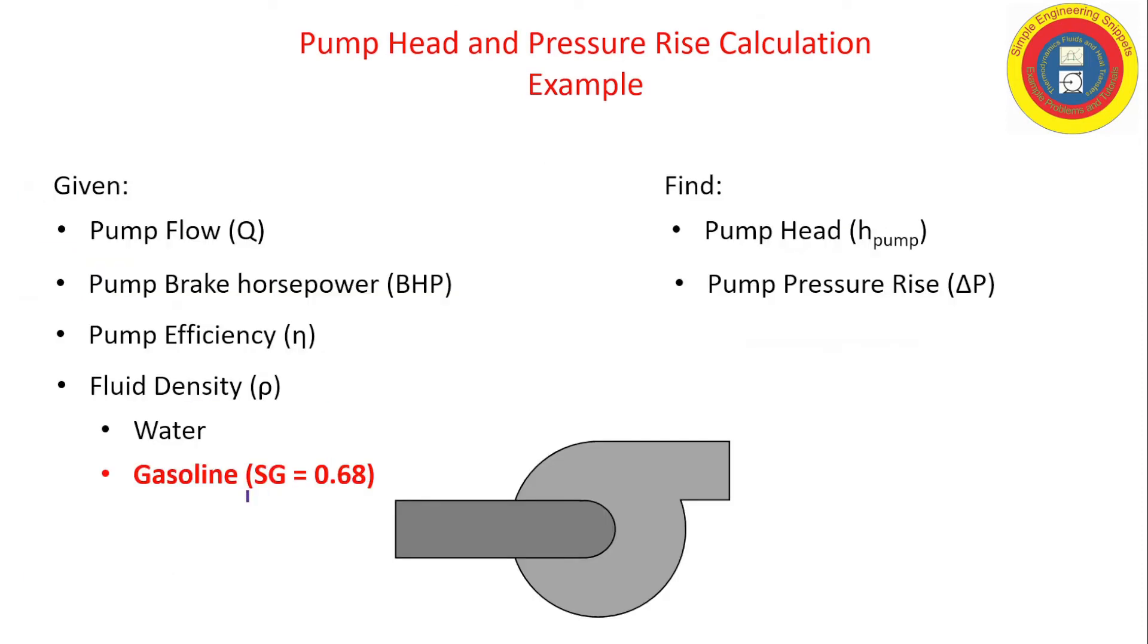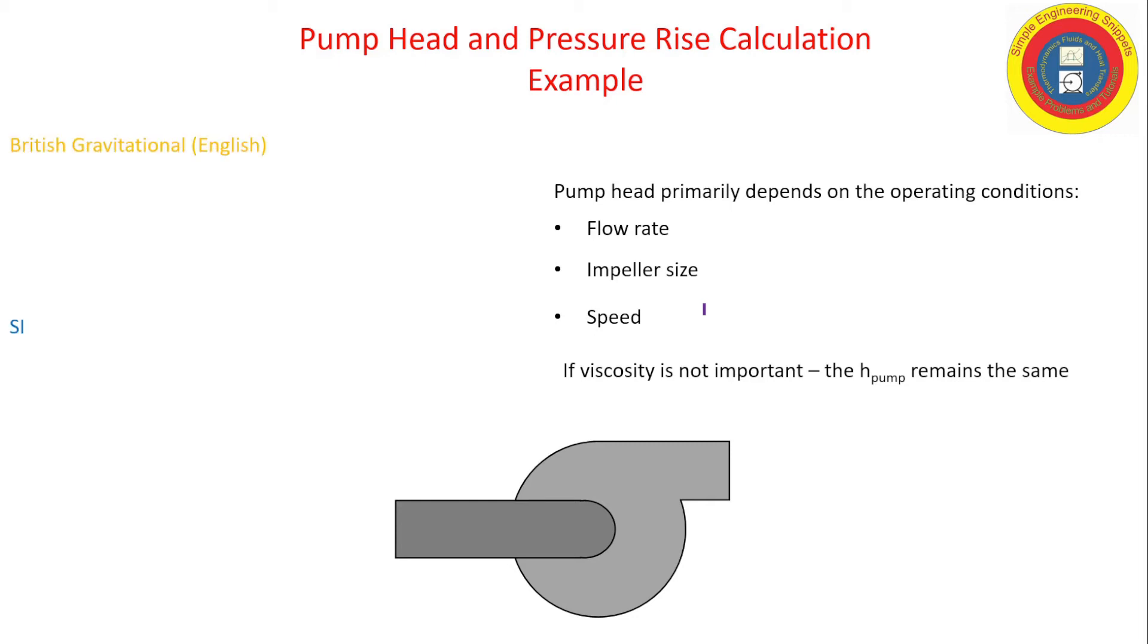And now let's repeat that for specific gravity 0.68 for gasoline. Okay, but before we dive into it, let's review what we mean by pump head. It's energy per weight, and pump head really depends upon flow rate, impeller size, and speed. Now this is true as long as the viscosity is not a major player, which is typical for most fluids.